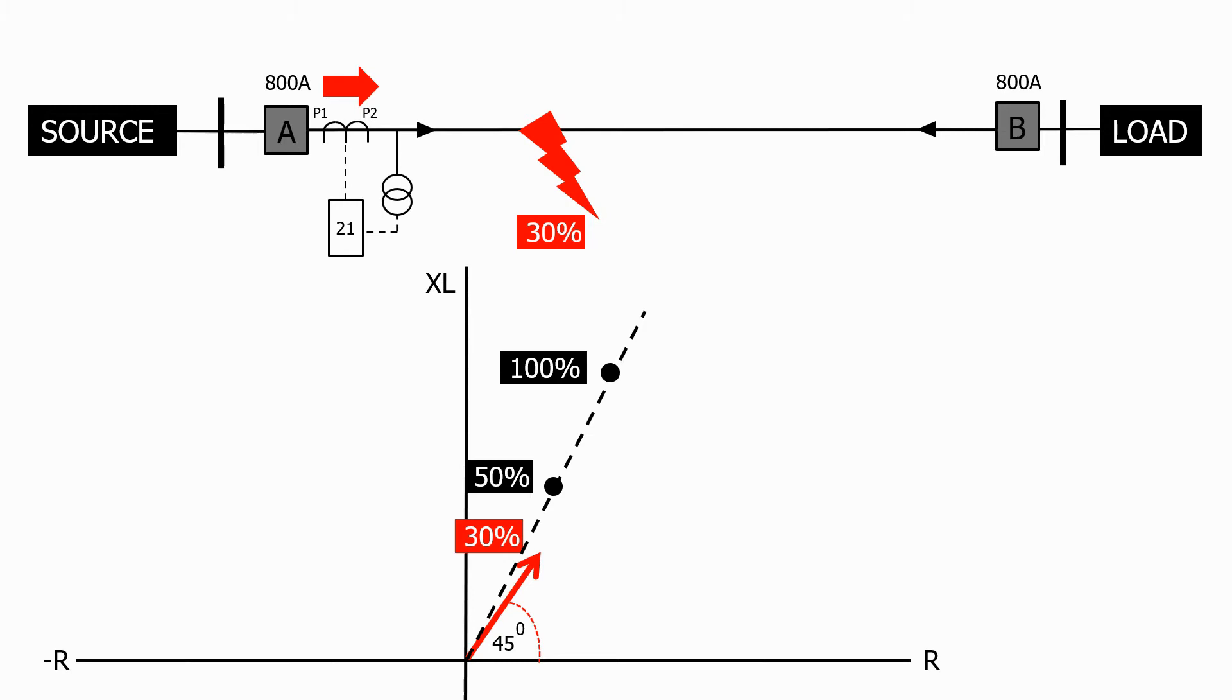And finally, at 30% of the line length, the resistance of the line now forms a large part of the line impedance value and the characteristic angle reduces substantially.